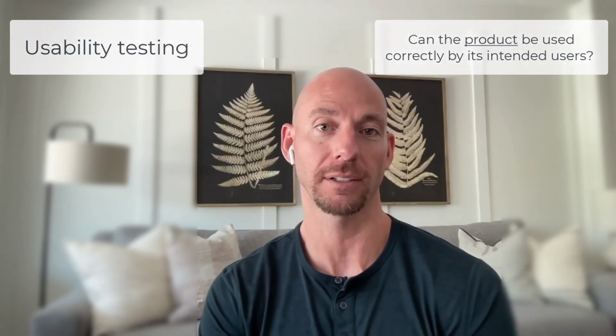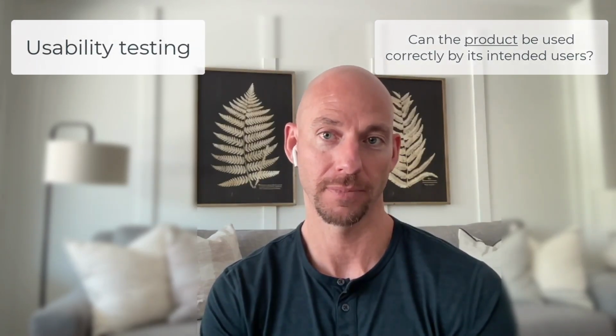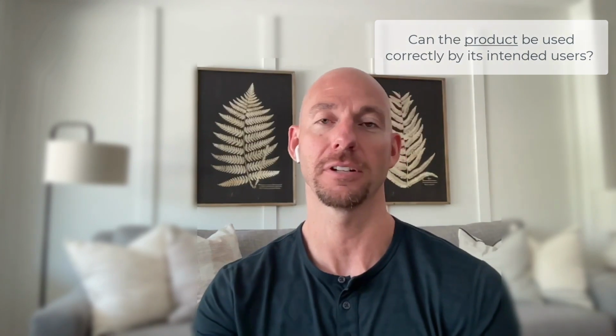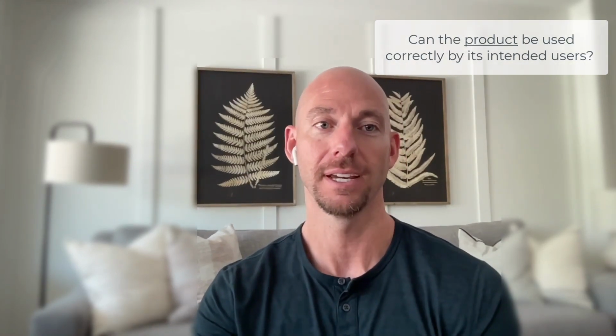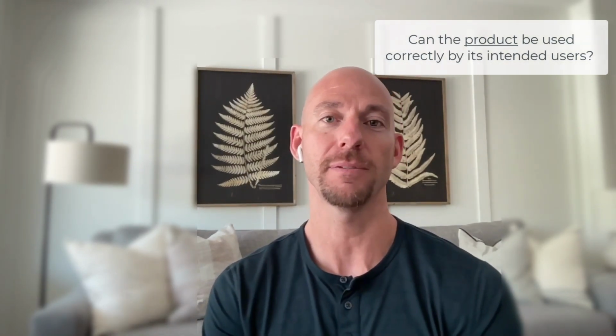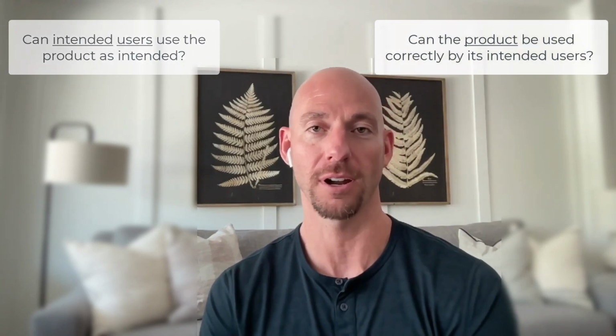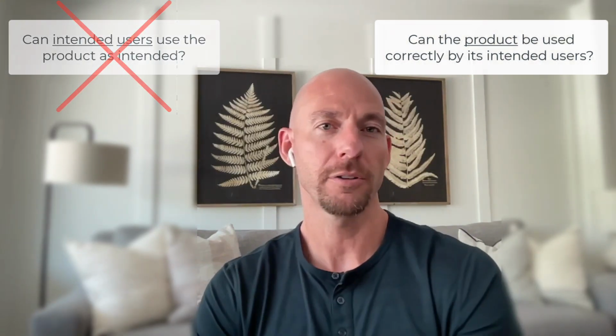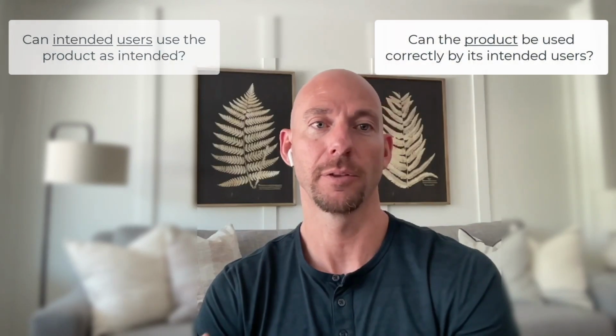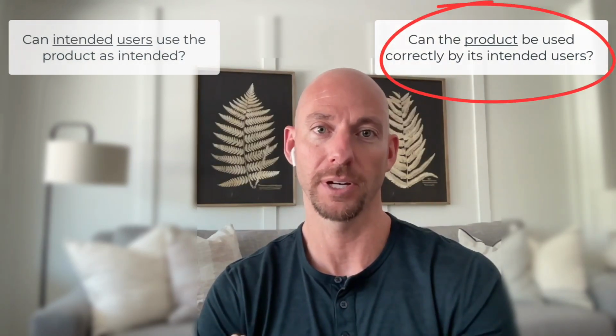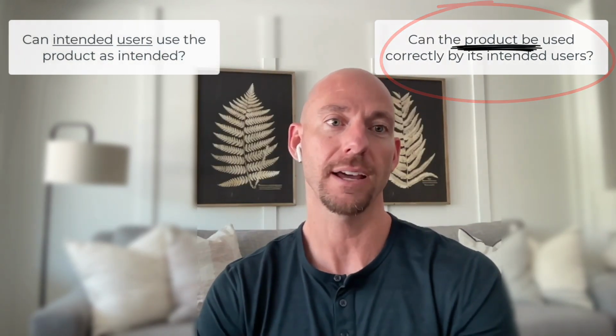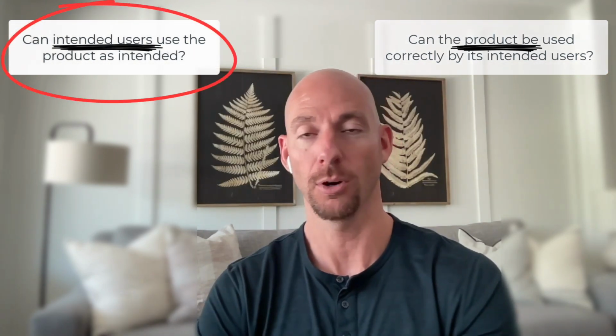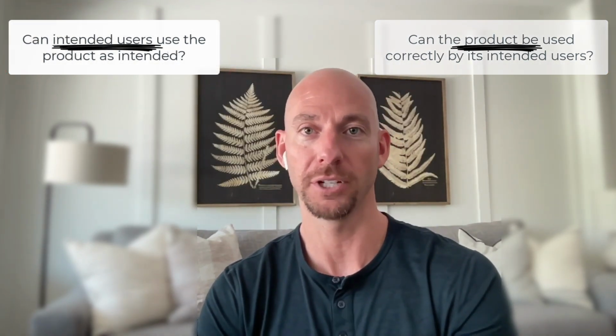Usability testing is a human factors and user experience research method designed to evaluate a product's ability to be used correctly by its intended users. I think it's worth making a special note that the purpose of usability testing is not to determine if intended users can use the product as intended. Although the two definitions are nearly identical, the former keeps the focus of the evaluation on the product, where the latter implies that the intended users, or the study participants, are the subject of the test.